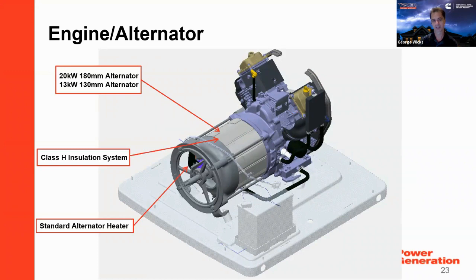Just some basic internals here. The alternator is a Class H insulation alternator, which is a technical term from the industrial world referring to insulation levels and classes. It has to do with the amount of copper windings and the temperature rise it's rated for. One nice feature is that every single unit has a standard alternator heater built in, right out of the box, rated to start down to 0 degrees. That's something Mark mentioned in the video.